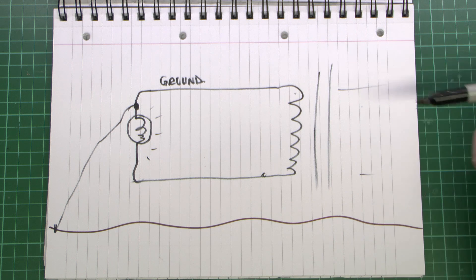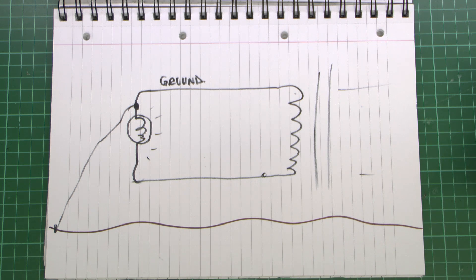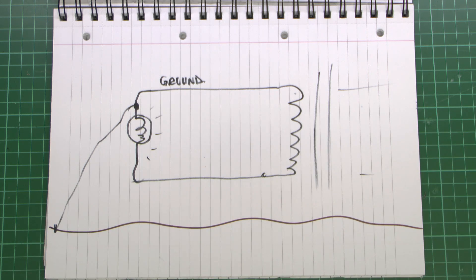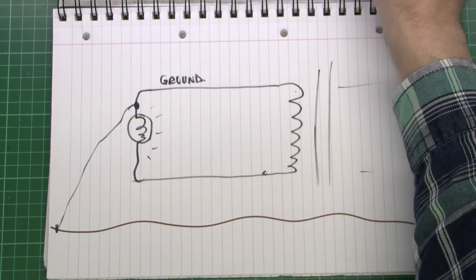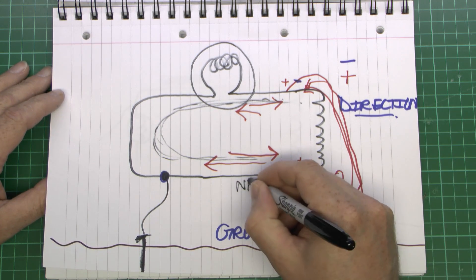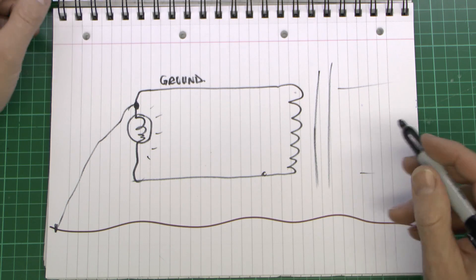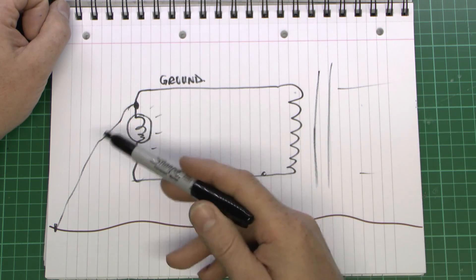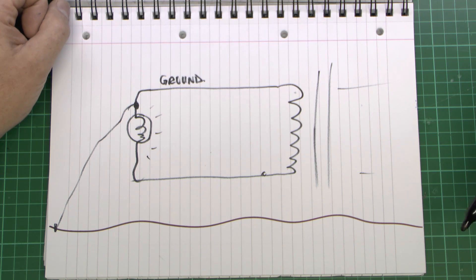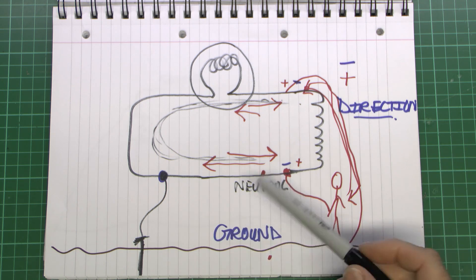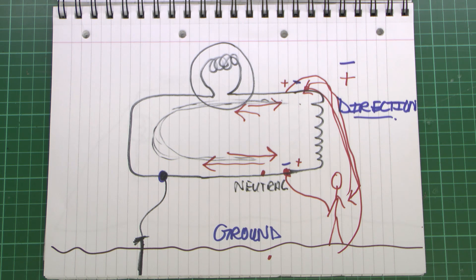And this is fairly likely to occur, because bearing in mind this whole street of property is supplied from a single transformer, as it's common in the UK, you've got no control over what happened in other people's houses. So at some point, your lovely isolated system would get connected to ground somewhere, and then you have no control over which one is going to be the one that kills you, and which one is the one that's safe. And therefore, it's much better to do what we did previously, and decide that this one is going to be the one that's connected to the ground, and therefore is the ground or the neutral wire, as it's called. Because then you know that whatever you've called the neutral will remain that way. And then the other one, of course, will be the live, whereas with this arrangement, a fault somewhere could mean either one of them, then you have no control over the situation. So all main systems are referenced to ground in this fashion, purely so that then you have control over which one is which, and then you know which is obviously the correct ones to connect in your bits of equipment.